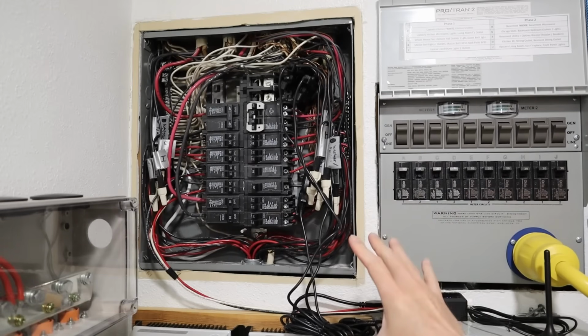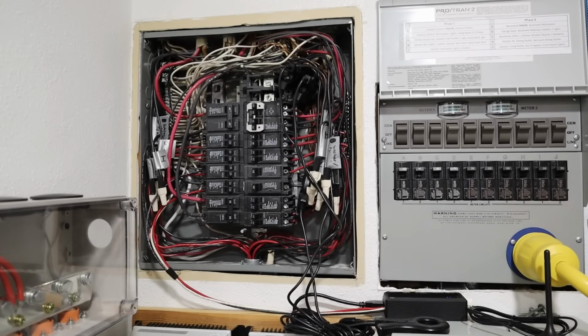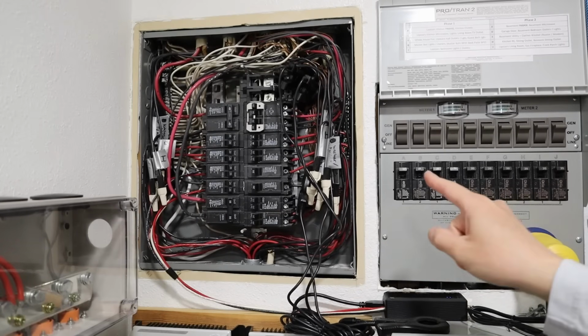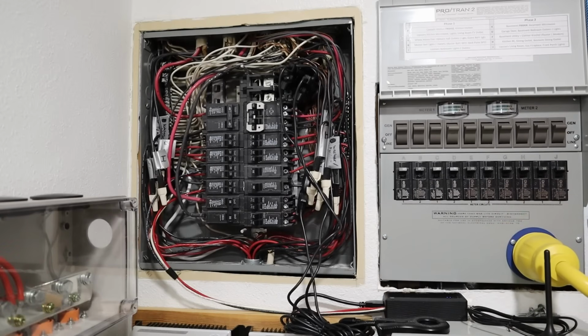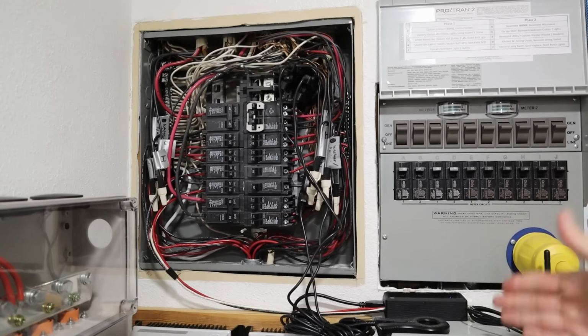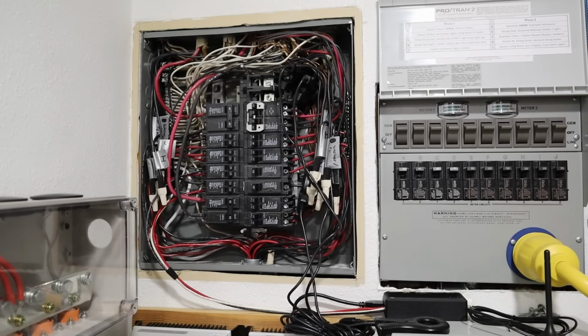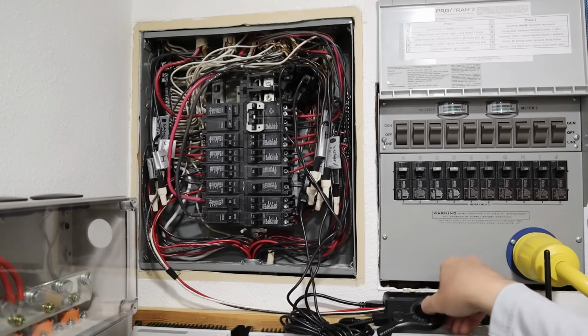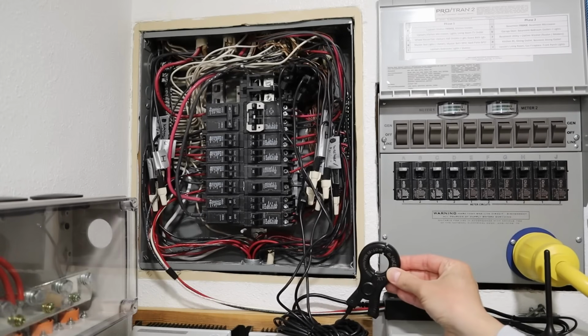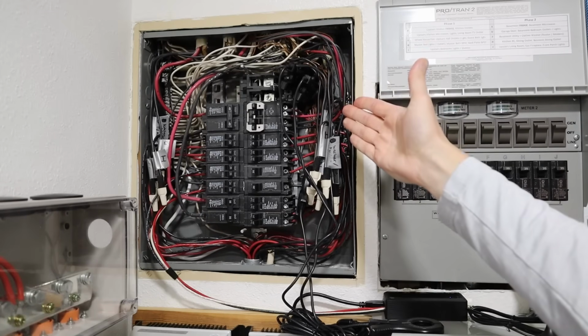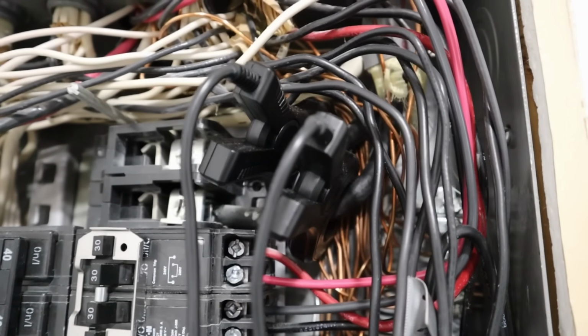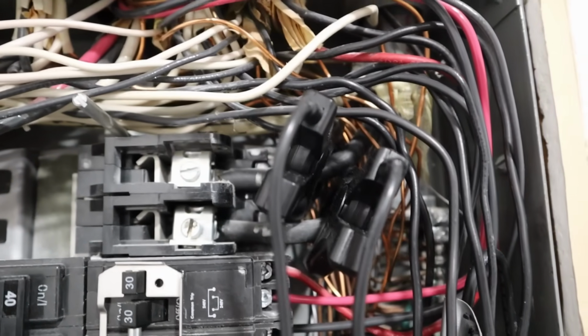So this is the main breaker box. I have the front panel removed so you guys can see all the wiring. Now just keep in mind, this 10 circuit transfer switch is also tied into this, so it looks a little bit more complicated than normal. Now, in order for the smart meter to function properly, it needs to measure the voltage and the amperage. Remember, volts times amps equals watts. So there are two inputs in order to measure the voltage and amperage. Now, first off, the unit comes with 4 of these clamps. 2 of them are designed for line 1 and line 2 input, so phase 1, phase 2, to measure the amperage coming in on each of those.